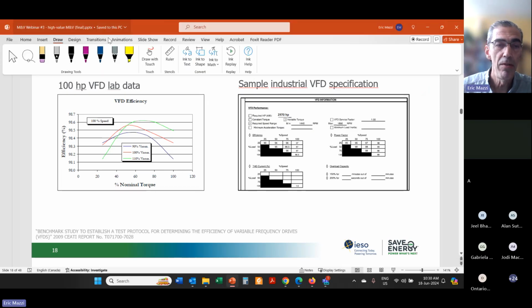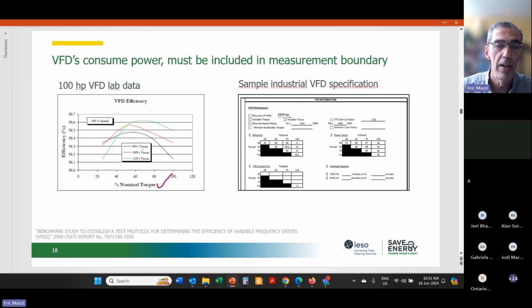As a general reminder, or for those who weren't aware, when VFDs are part of the system, the VFDs consume power themselves. So that needs to be counted and measured in the M&V. I'm sure many of you know this, and just as an example, on the left here we have a chart that shows the VFD efficiency, where a VFD efficiency of 98% would mean that the VFD itself consumes 2% of the power that is fed to the motor. And that VFD power consumption, or VFD efficiency, will change with certain variables such as motor torque or load. It will change if there are changes in the system voltage, and of course the speed.